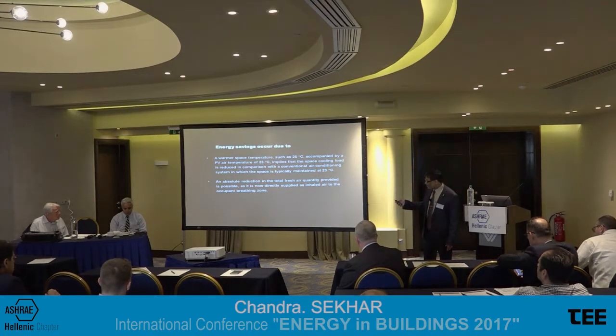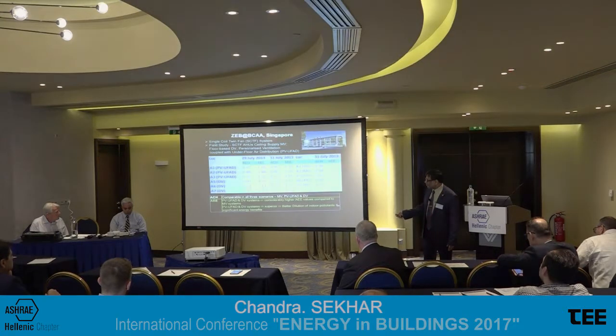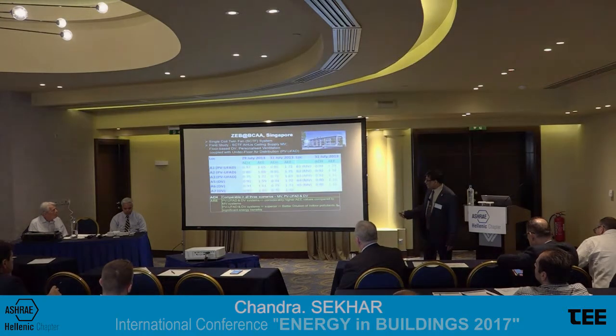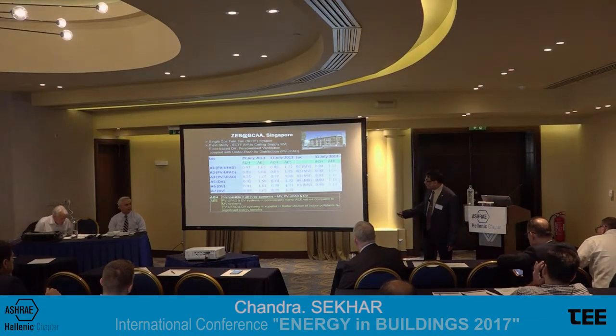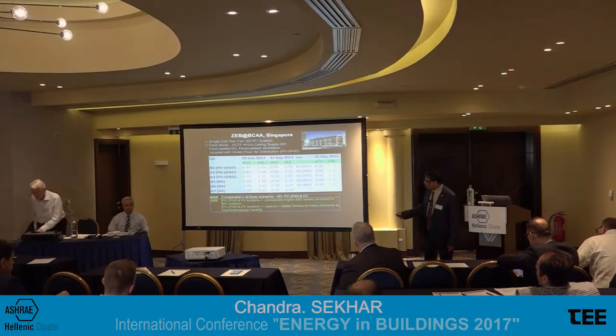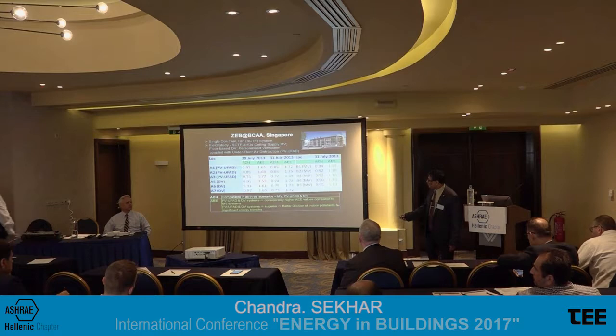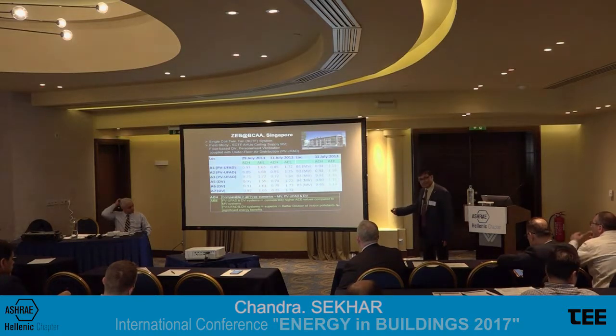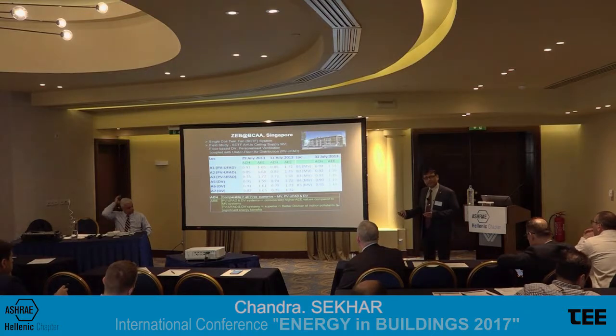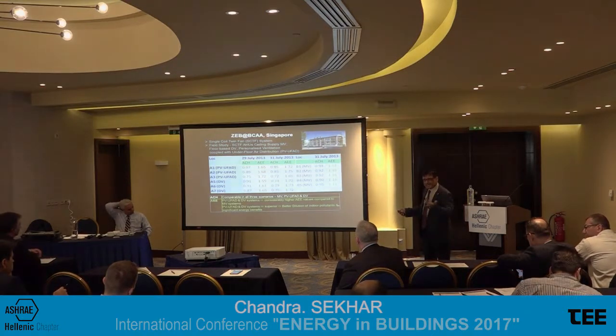Personalized ventilation systems do have that potential to help us save energy. In the same zero energy building, we tried personalized ventilation as well in one occupied office space. The air exchange effectiveness with PV systems was almost always more than 1.6, compared to 1.1 with conventional systems in this case - distinctly different and better compared to conventional systems.